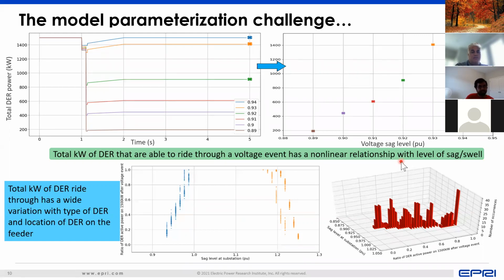I mean, we all talk about, and we continue to see money flowing into the densification, the electrification, but what this proves here is that we will see an increase in complications on these trip models that you have as voltage variance change. Exactly. And not just voltage variance, it's also the increase in complexity as you have different types of DER coming in. Like, for example, a DER may have a lifetime of maybe 20 years, but in that 20 years period, the standards would change. So now at a given point in time, one particular feeder may have DER which follow 3 different standards. So let's say even if you go from 2003 to 2023.